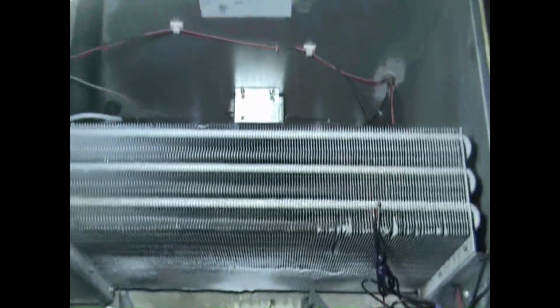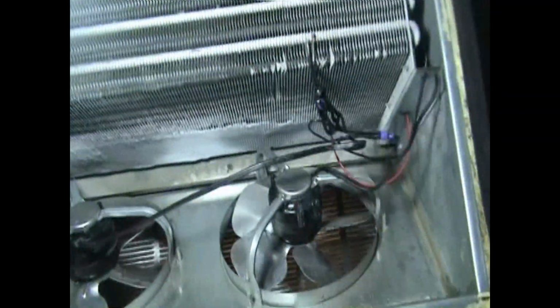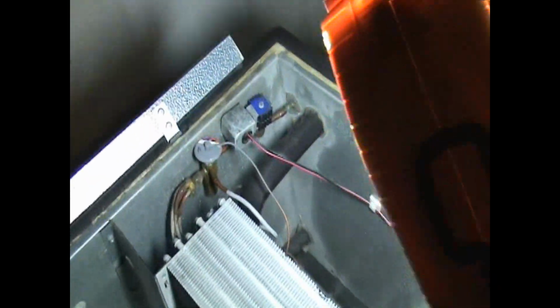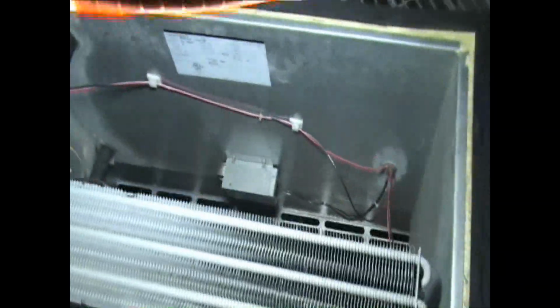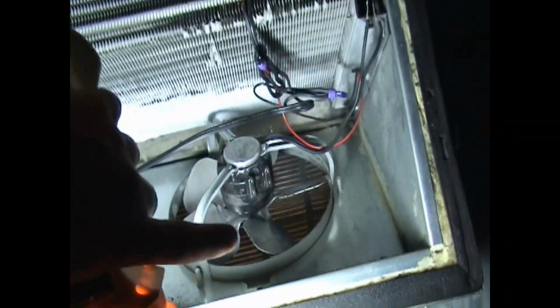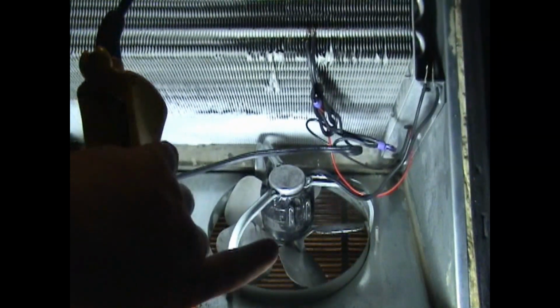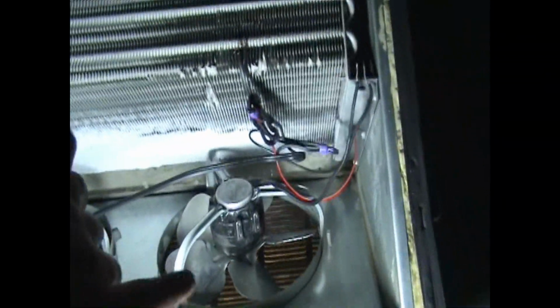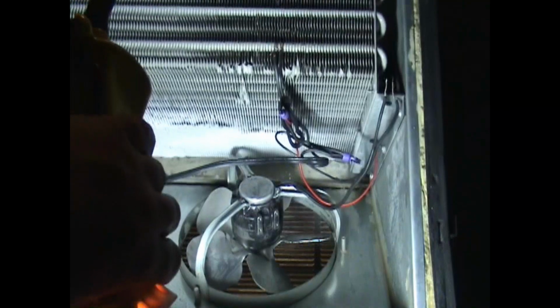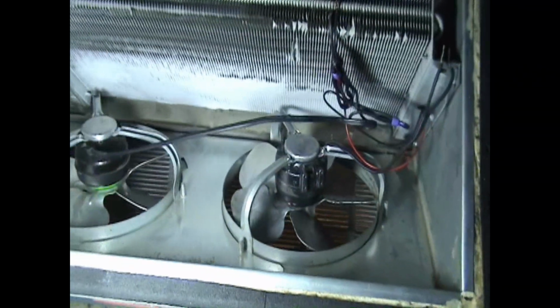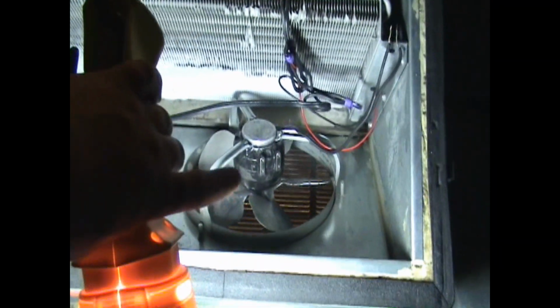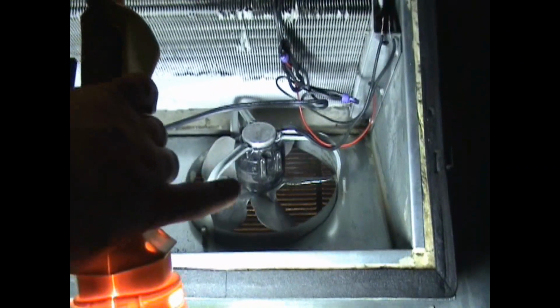So here's what we got with that box opened up. There's the evaporator coil, two fan motors, expansion valve, solenoid valve and coil, and that box right there is the temperature control. So what we got to do is change out this fan motor. This is a temporary one I put in there yesterday just to get the unit back up and running. The RPM on this is slower than what it should be, so I gotta take this out and put in the new one.